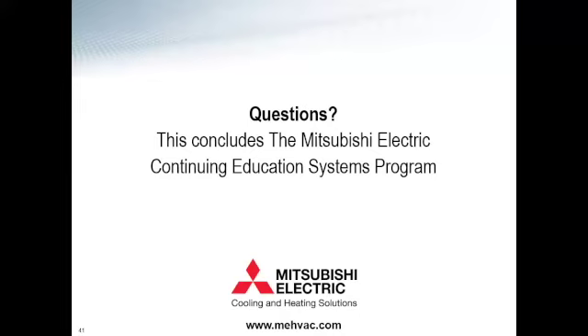Do you have a very simplified cost number, how much more the heat recovery costs? Sure. This is very much ballpark, but if you're looking at a heat pump system versus a heat recovery system, you're going to be somewhere between 15 and 20% more expensive on the heat recovery side. However, one thing to keep in mind is that although it is more expensive on the installation or equipment cost side, your energy usage will be significantly lower, so your energy costs should be pretty well evened out.